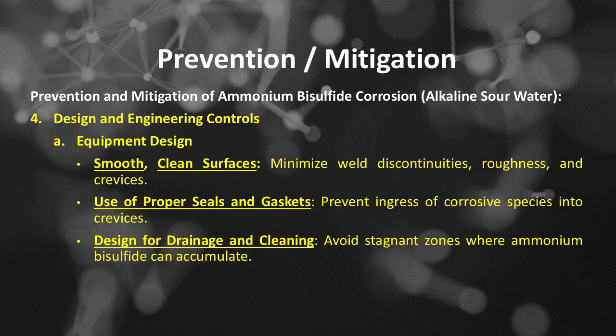Number 4 is design and engineering controls, which includes, number A, equipment design: smooth, clean surfaces, minimizing weld discontinuities, roughness, and crevices; use of proper seals and gaskets to prevent ingress of corrosive species into crevices; and design for drainage and cleaning, avoiding stagnant zones where ammonium bisulfide can accumulate.